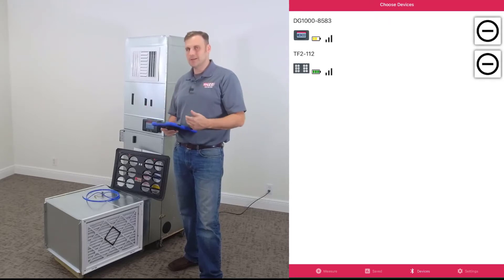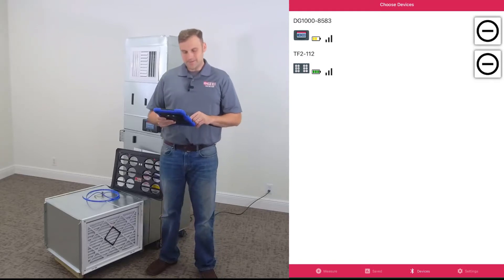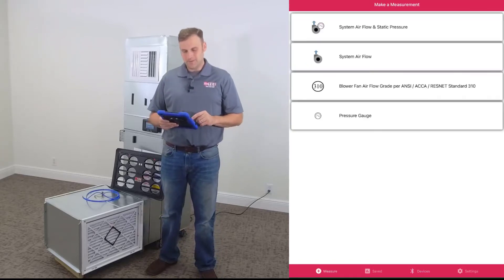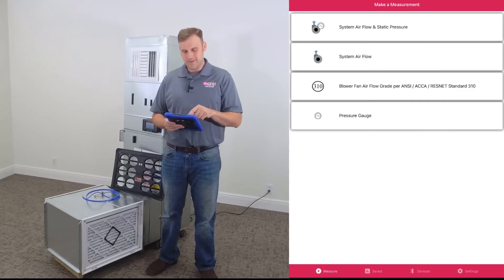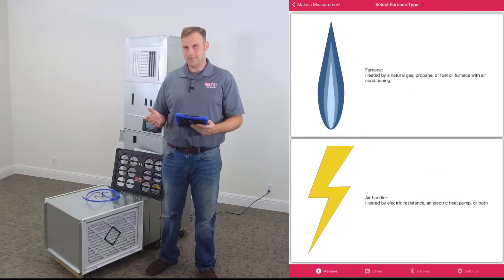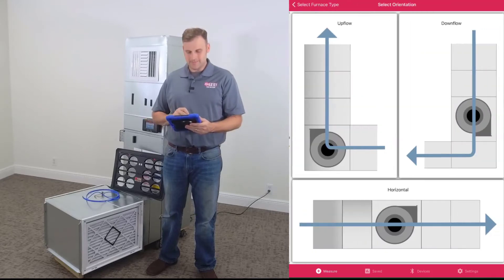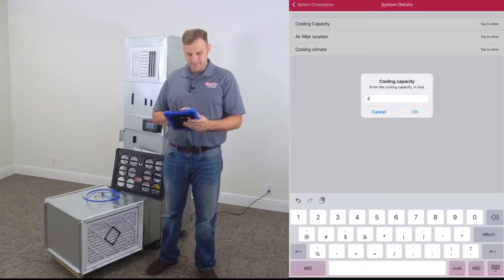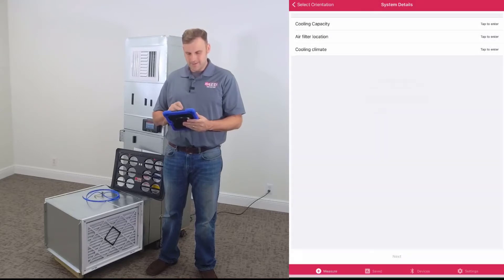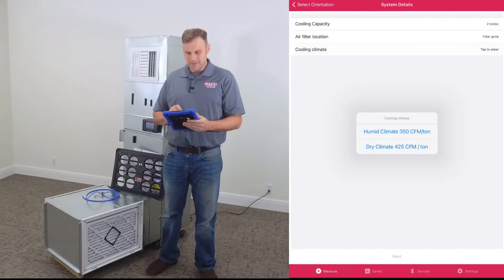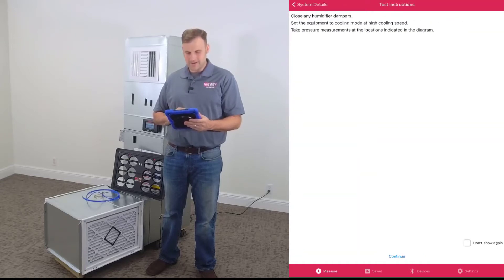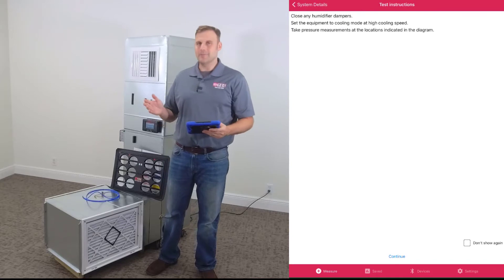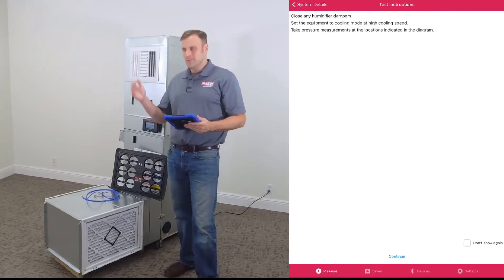Let's go to Measure, select our workflow. We're going to do the second one down: System Airflow. We got to make a quick few selections: air handler upflow, cooling capacity two tons, air filter location filter grill, cooling climate 350 CFMs per ton. Let's click Next at the bottom.